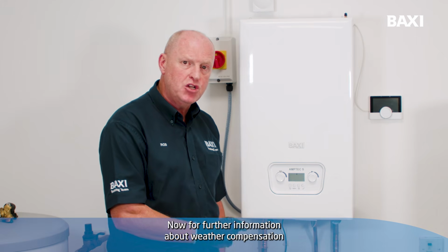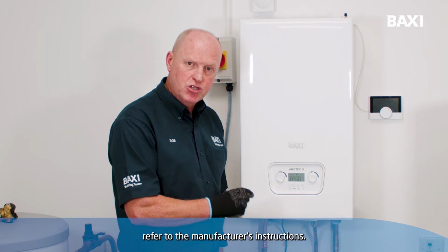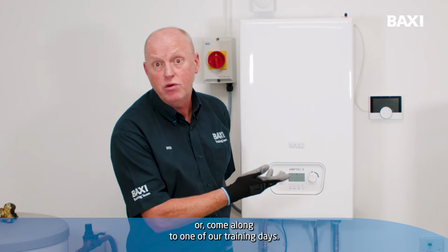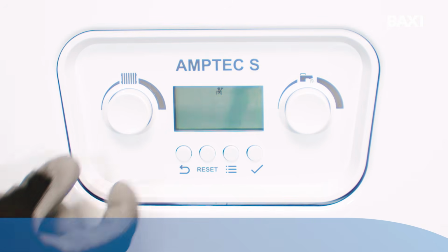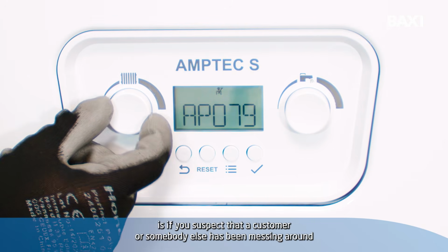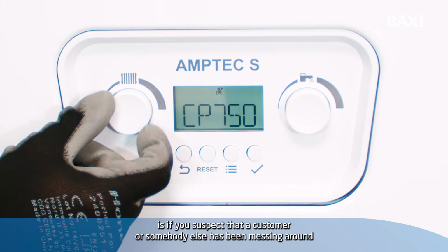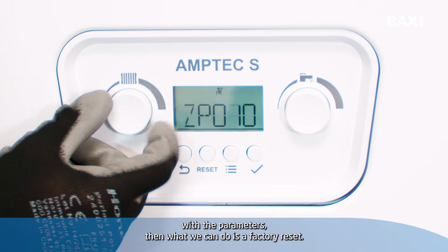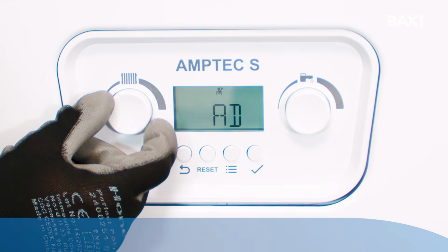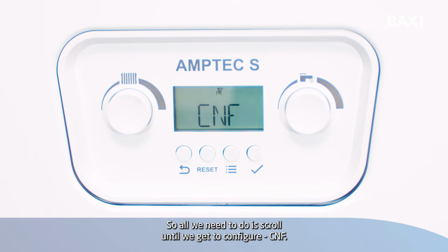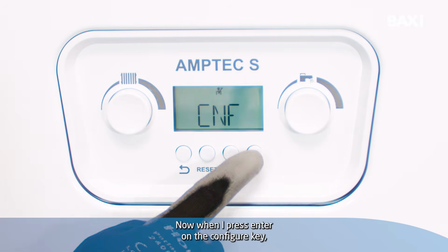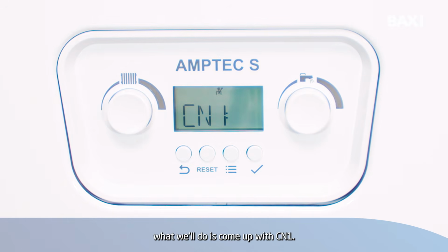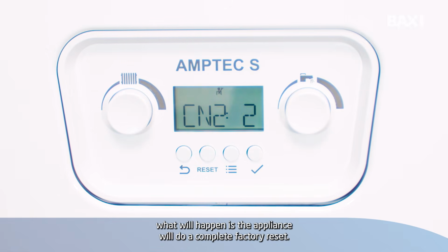Now for further information about weather compensation, refer to the manufacturer's instructions or come along to one of our training days. But a really useful one is if you suspect that a customer or somebody else has been messing around with the parameters, then what we can do is a factory reset. So all we need to do is scroll until we get to configure, CNF. Now when I press enter on the configure key, we'll come up with CN1.